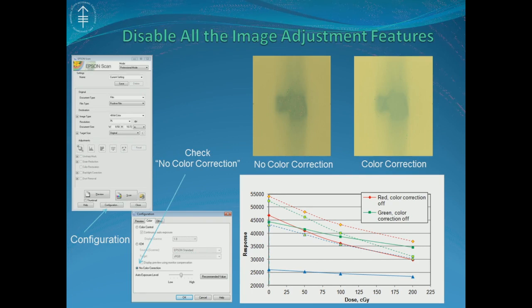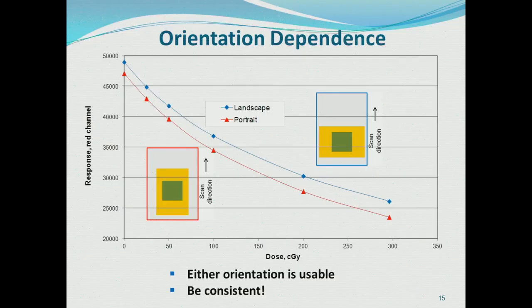First, the scanner must have a transparency adapter. Use professional mode. And choose film and 48-bit color for multi-channel dosimetry. And click on the configurations and turn off the color correction, so all the icons are grayed out. When you scan, either landscape or portrait direction is usable, but it has to be consistent for all films. I prefer to use portrait orientation, which is the scanning direction going through the longer side of the film.